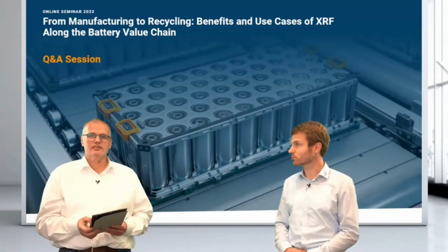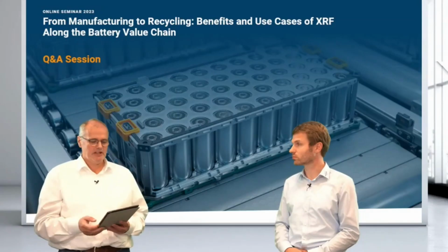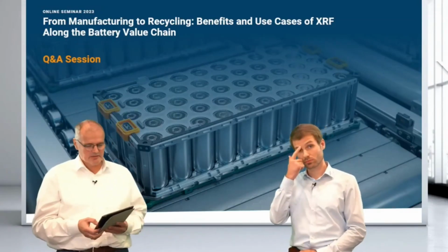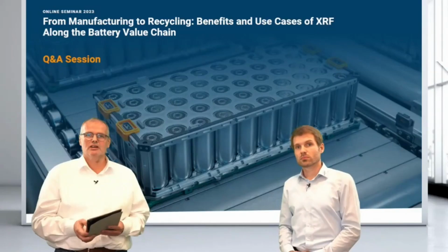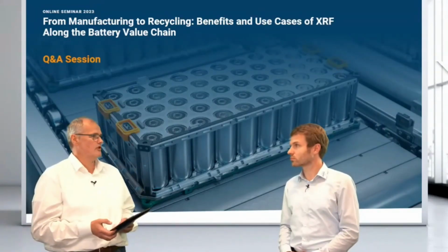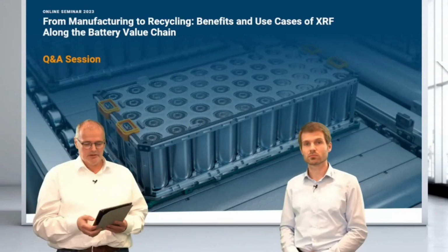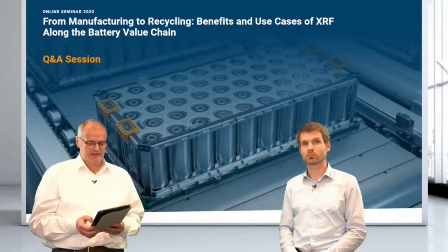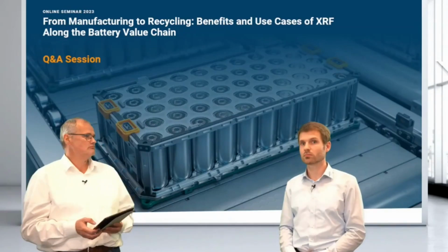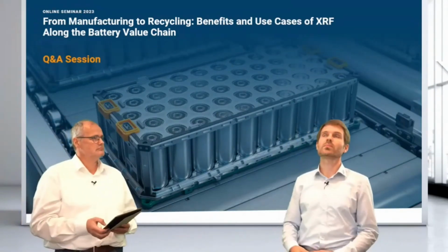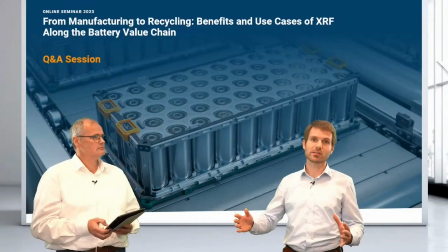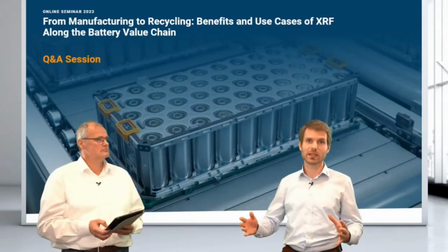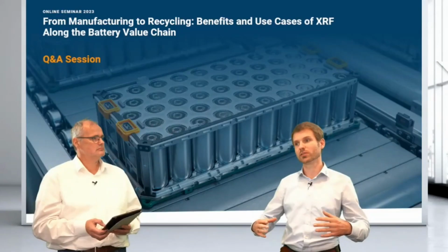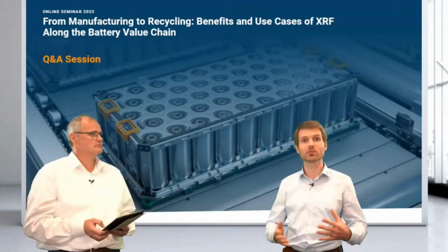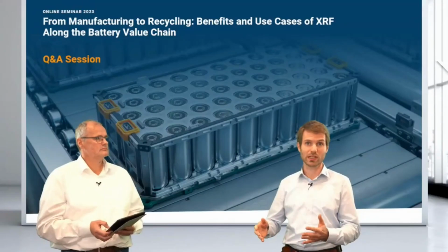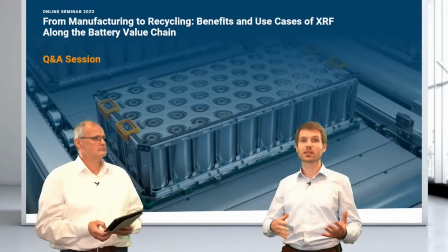Yeah. There's one question which is kind of interesting because this might come from an ICP user. The calibration curves for liquids we have shown are close to a correlation coefficient of 1. But what about the range over which you get this level of linearity? Yeah, so the linearity is relatively wide, but there are also factors at which the linearity goes a bit off, and this is when you have what Kai said, the matrix effect. But our software is essentially capable of compensating that.